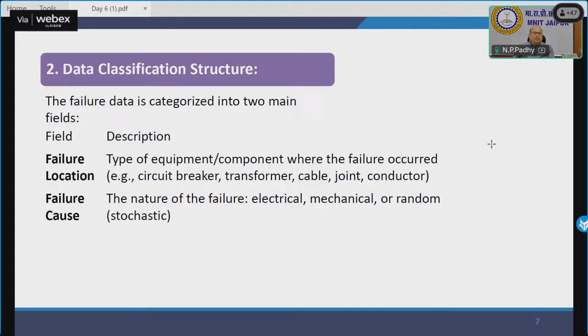For data classification, we look at the type of equipment or component where the failure occurs -- circuit breaker, transformer, cable, joint, conductor -- and the failure cause. For example, if aluminum binding causes a conductor to fail frequently, you might consider copper binding or another material instead. The nature of the failure also matters -- whether it's electrical, mechanical, or something random that nobody can explain, where everything seems perfect but there's still a failure. That needs to be treated as stochastic.